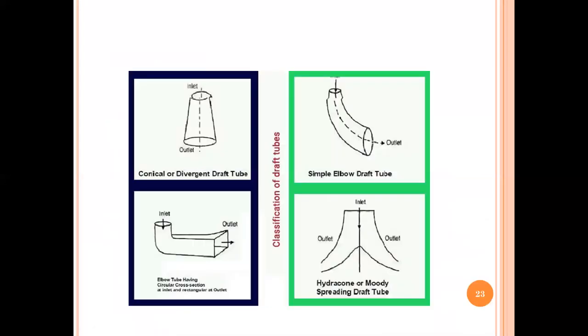There are four types of draft tubes. The first is a conical or divergent draft tube used in the Francis turbine. The second is an elbow tube with circular cross section at inlet and rectangular outlet, used for the Kaplan turbine. The third is a simple elbow draft tube with both circular sections but larger outlet area. The fourth is the moody spreading draft tube. The last two are used in special cases depending on site conditions.